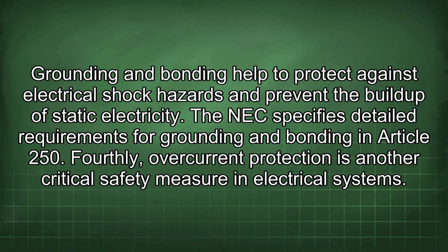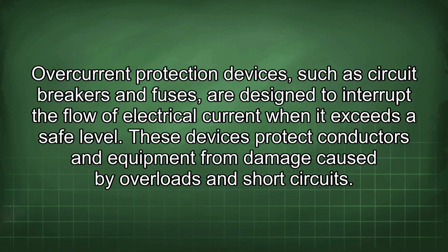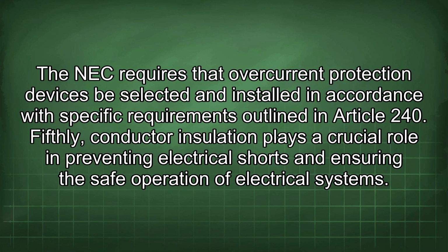Fourthly, overcurrent protection is another critical safety measure in electrical systems. Overcurrent protection devices, such as circuit breakers and fuses, are designed to interrupt the flow of electrical current when it exceeds a safe level. These devices protect conductors and equipment from damage caused by overloads and short circuits. The NEC requires that overcurrent protection devices be selected and installed in accordance with specific requirements outlined in Article 240.